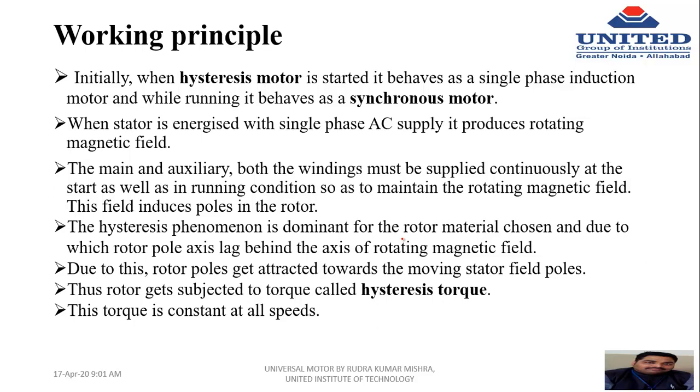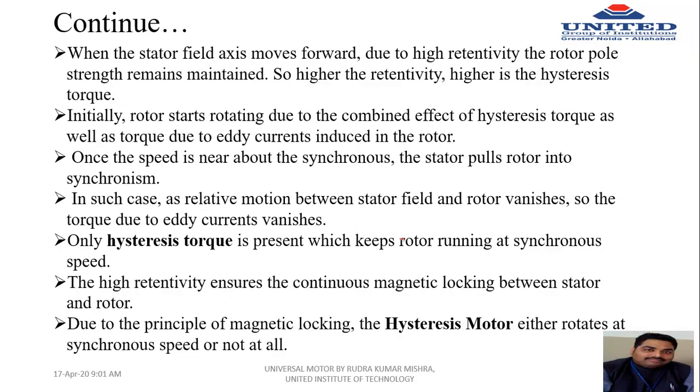Due to this, rotor poles get attracted towards the moving stator field poles. Thus the rotor gets subjected to a torque called hysteresis torque. This torque is constant at all speeds. When the stator field axis moves forward, due to high retentivity the rotor pole's strength remains maintained. So the higher the retentivity, the higher is the hysteresis torque.